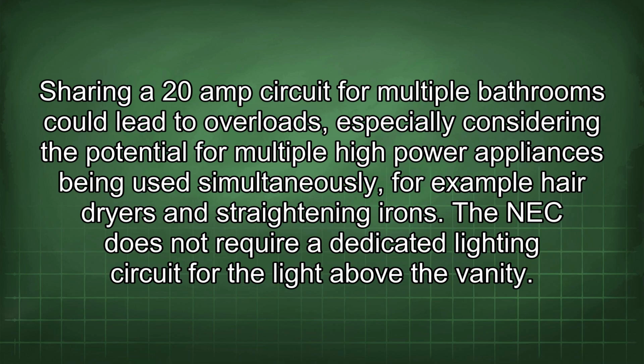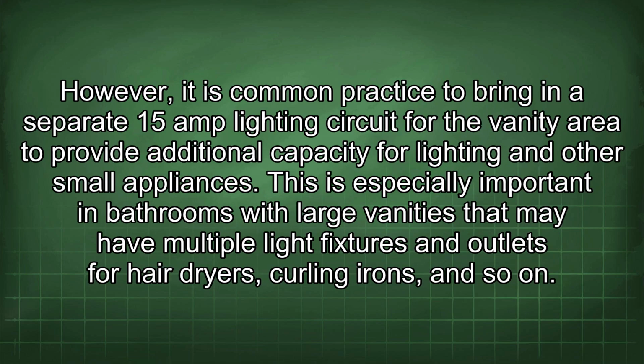The NEC does not require a dedicated lighting circuit for the light above the vanity. However, it is common practice to bring in a separate 15-amp lighting circuit for the vanity area to provide additional capacity for lighting and other small appliances.